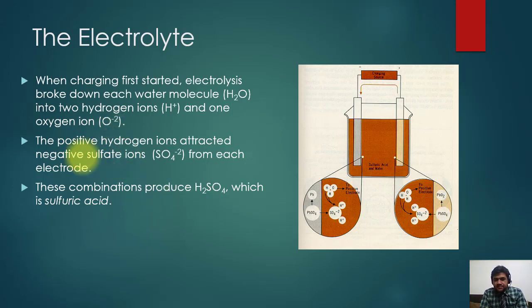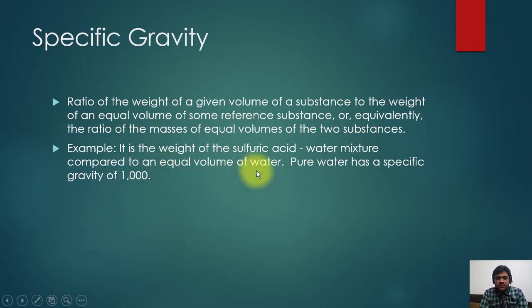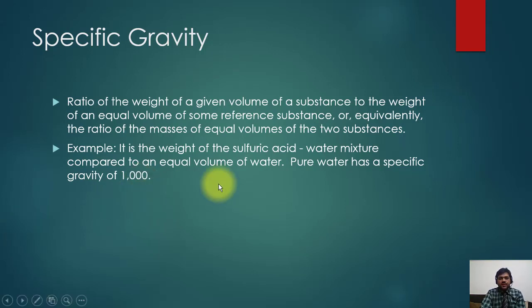Specific gravity is the ratio of the weight of a given volume of a substance to the weight of an equal volume of a reference substance — equivalently, the ratio of the masses of equal volumes of two substances. For example, it compares the weight of a sulfuric acid-water mixture to the equal volume of pure water. Pure water has a specific gravity of one. So if we say the specific gravity of the electrolyte is 1.2 or 1.3, it means it is 20% or 30% heavier than the same volume of water.